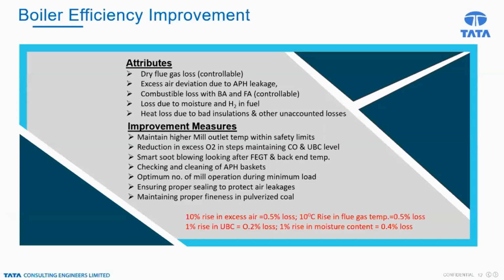The first one is boiler efficiency improvement. This is very obvious because the plant heat rate is directly linked to the boiler efficiency. If you have the boiler efficiency equal to the design value, obviously the plant heat rate would be better. So what are the various factors affecting the boiler efficiency? One is the dry flue gas loss. Second is the excess air deviation, excess air due to the RAPH, air preheater, leakage. There are combustible losses in the bottom ash and fly ash, because unburned carbon going along with the ash will lower the boiler efficiency.